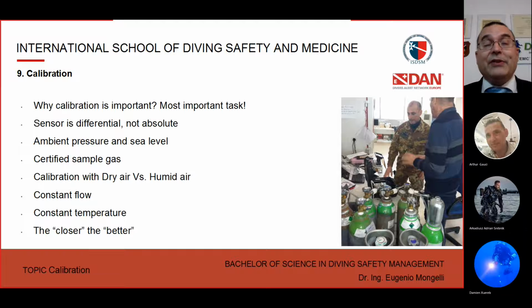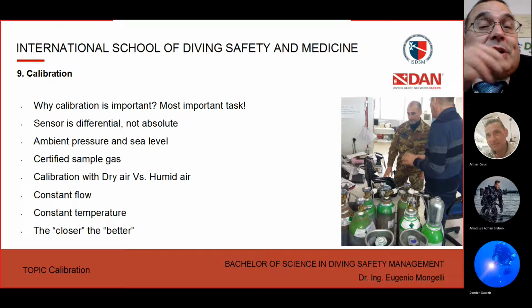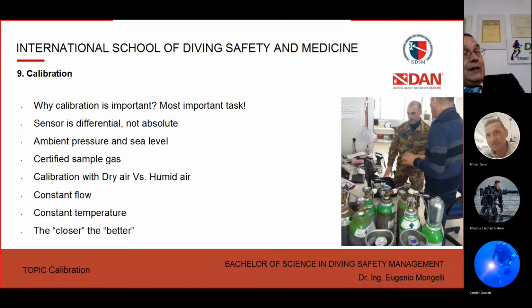Another tip is: the closer the better. What does it mean? It means that the closer you do the gas calibration to the analysis point, to the target gas, the better accuracy you may have. And not only for the concentration of the gas, but also with the carrier gas, meaning the inert gas, the nitrogen or helium.